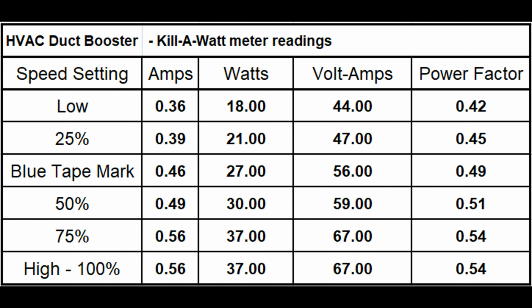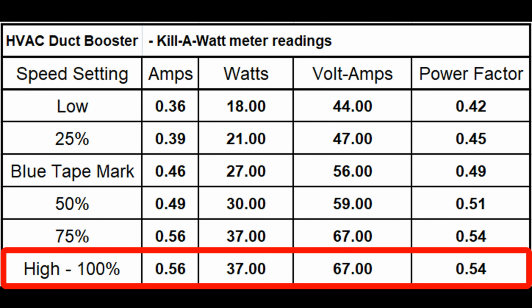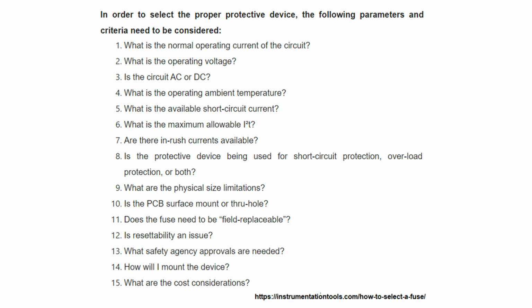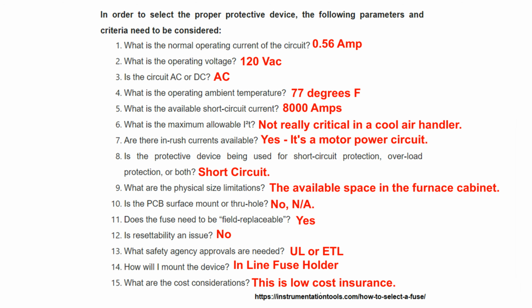Now that I have the duct booster power details I need, I can select my fuses. Let's have a look at this helpful list of fuse selection criteria I found at instrumentationtools.com. In the interest of time, I'll fast forward to show my answers. The normal operating current is 0.56 amps at 120 volts AC. I actually measured the ambient temperature by the furnace control board and it was 68 degrees, but I'm going to say 77 degrees because it'll be warmer in the summer.